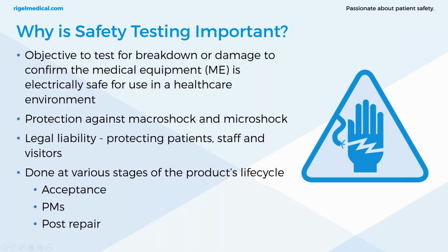PPMs and post-repair safety tests, regular maintenance carried out by biomeds, the end users in healthcare, help to detect any potential defects. It should also be mentioned that there is potential risk in some cases from fraudulent devices, not so much in the modern world, but there are cases where fraudulent devices and parts slip through the net, and if this occurs, then electrical safety checks, visual checks, and performance testing with performance analyzers will likely detect any problems.